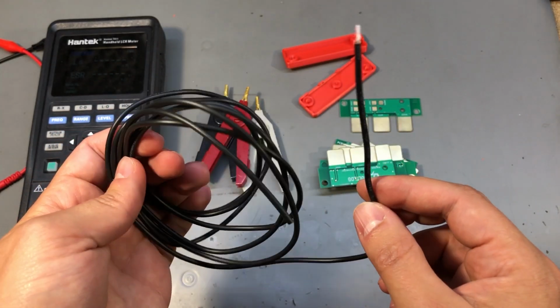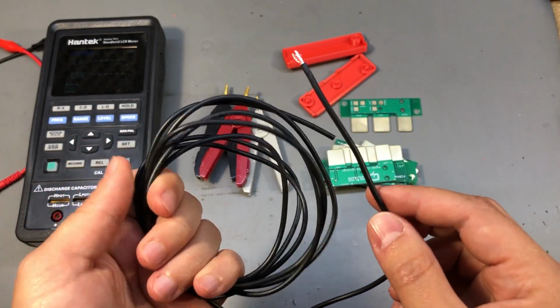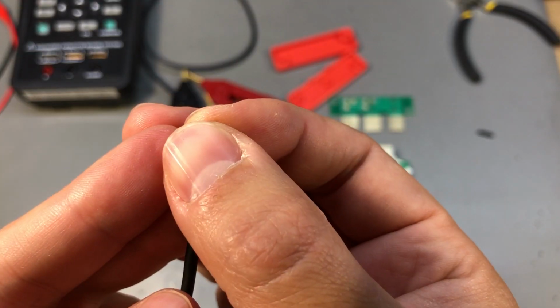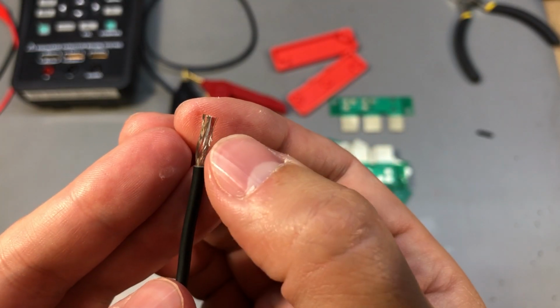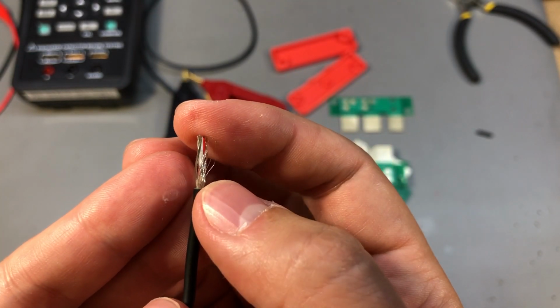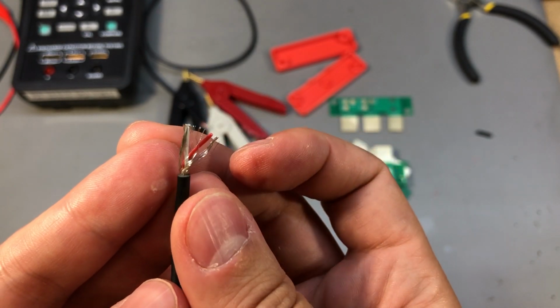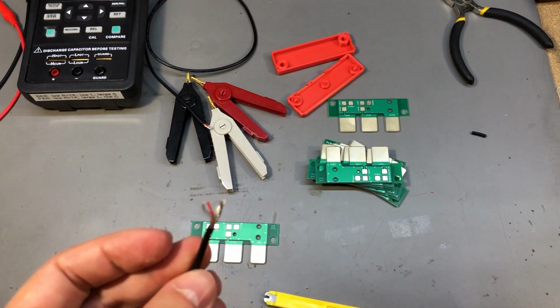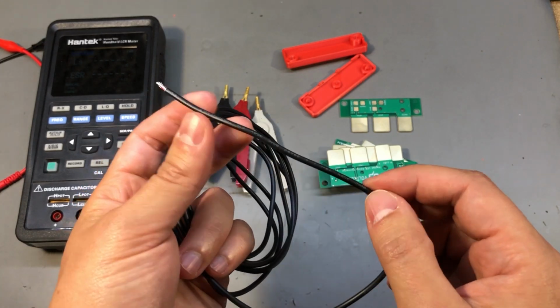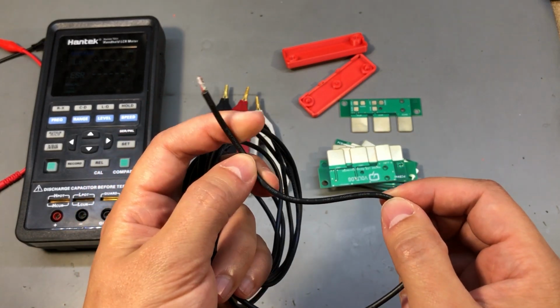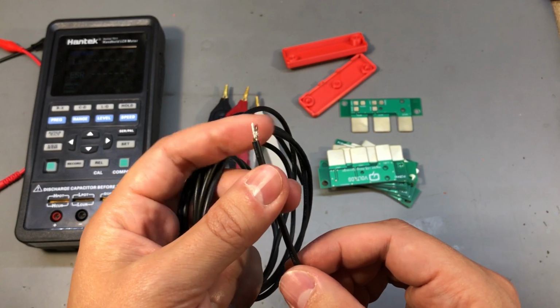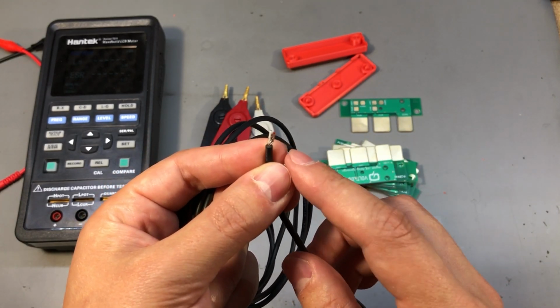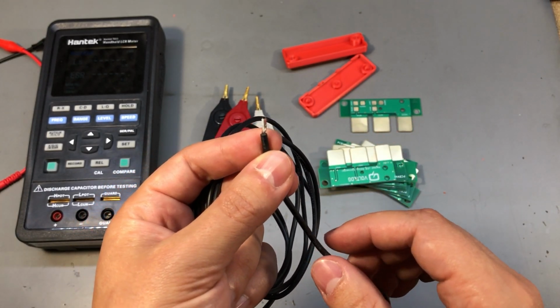As for the connection wires that go between the clips and the connector, I got some of this 28 AWG 2-wire shielded cable. This should be thin enough to still be flexible and at the same time still provide good connection. And we are talking about small currents here, so 28 AWG is gonna be fine. Ideally, we want this cable shielded and we want the shield to be connected to the guard terminal on the instrument.